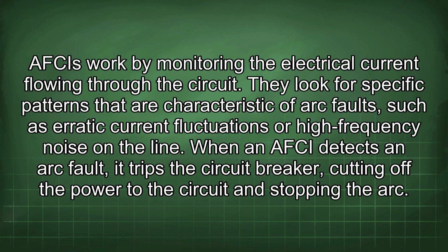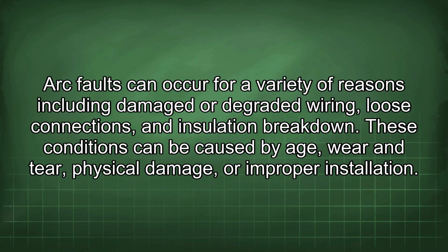AFCIs work by monitoring the electrical current flowing through the circuit. They look for specific patterns that are characteristic of arc faults, such as erratic current fluctuations or high-frequency noise on the line. When an AFCI detects an arc fault, it trips the circuit breaker, cutting off the power to the circuit and stopping the arc. Arc faults can occur for a variety of reasons, including damaged or degraded wiring, loose connections, and insulation breakdown. These conditions can be caused by age, wear and tear, physical damage, or improper installation.